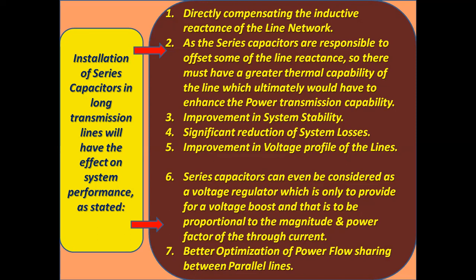Number 6, series capacitors can even be considered as a voltage regulator, which provides a voltage boost that is proportional to the magnitude and power factor of the through current. Number 7, better optimization of power flow sharing between parallel lines.